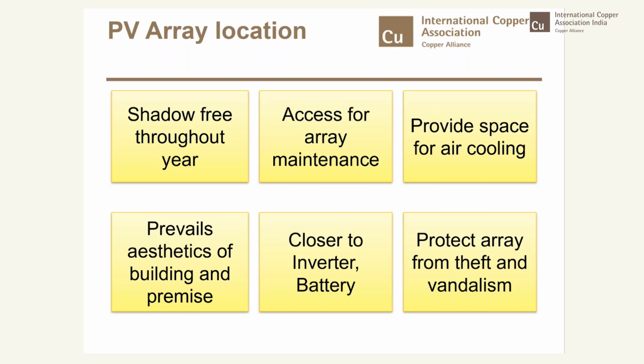And he also needs to keep some space for cooling the solar modules if it is a rooftop installation on a slanting roof, which generally people do not follow. Then it has to also blend with the prevailing aesthetics of the building and the premise. If it is a battery system, see that the inverter and batteries are closely installed, so that the wiring length can be reduced, and thereby the energy losses, power losses and voltage drops can be reduced to a larger extent. And then most importantly, protecting the array from theft and vandalism. So array location is the first crucial step for a project engineer.